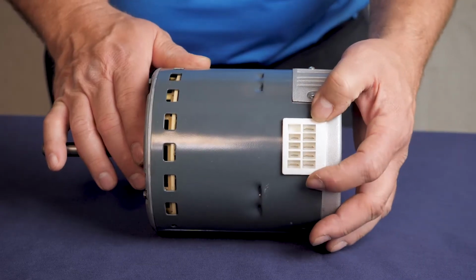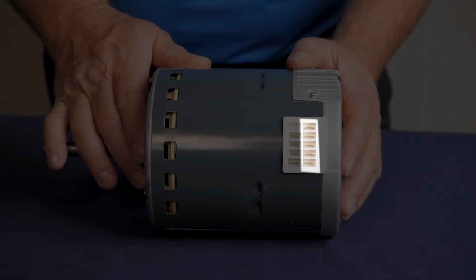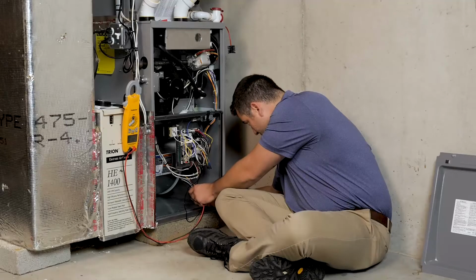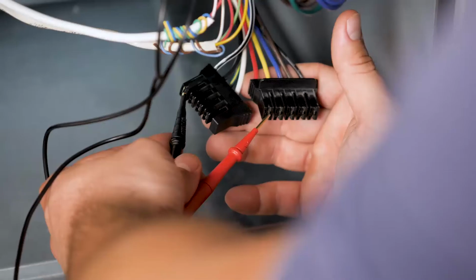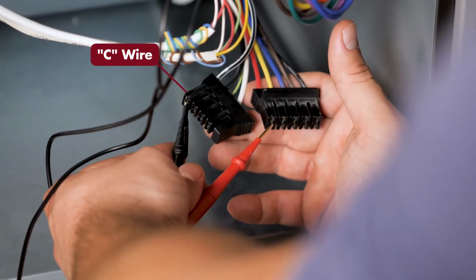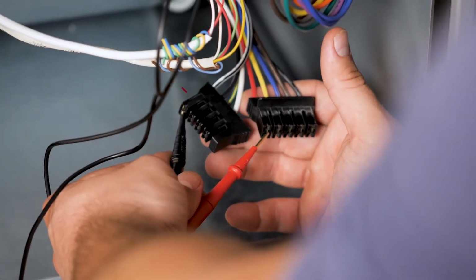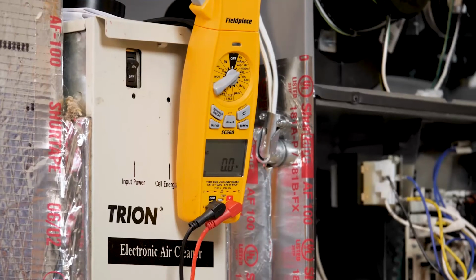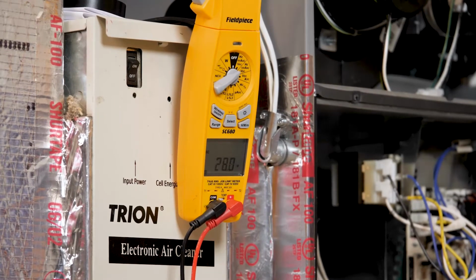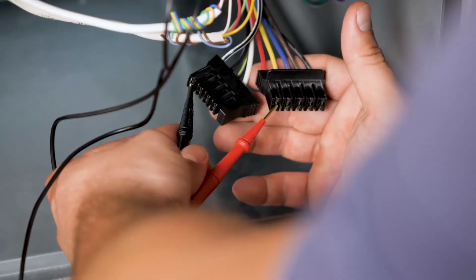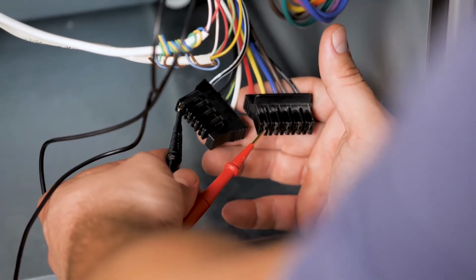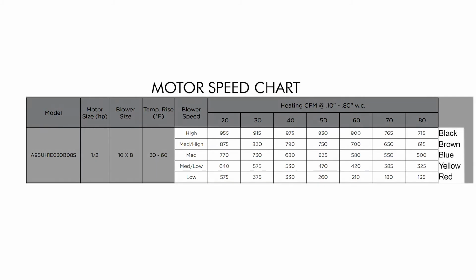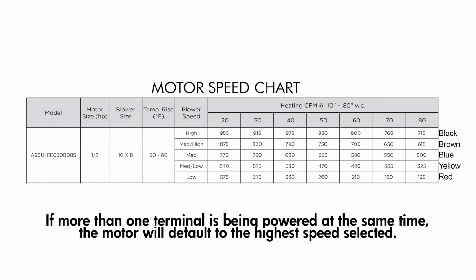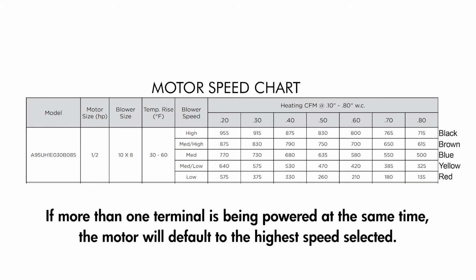On the X13 motor, the second plug has up to 5 speed connections. You will have to test for 24 volts from one or more of these wires to the C wire, which is on the high voltage plug. The motor will require both the high voltage as well as a control voltage coming to at least one of the low voltage motor terminals. Each of the control voltage terminals give the motor a command for a specific speed. If more than one terminal is being powered at the same time, the motor will default to the highest speed selected.